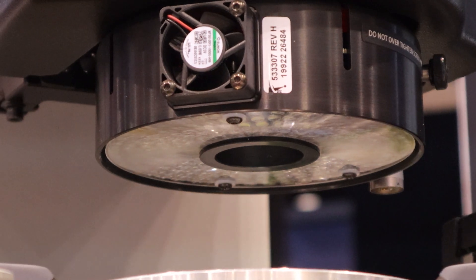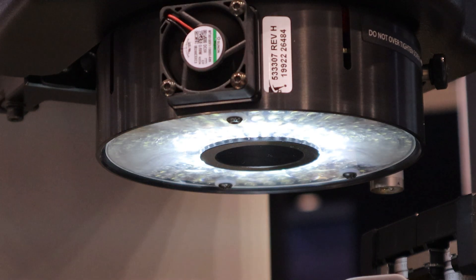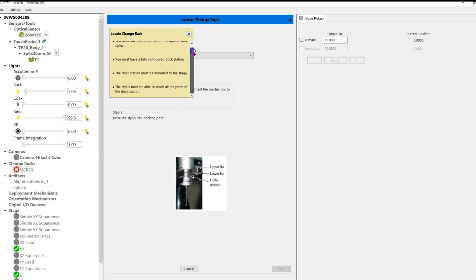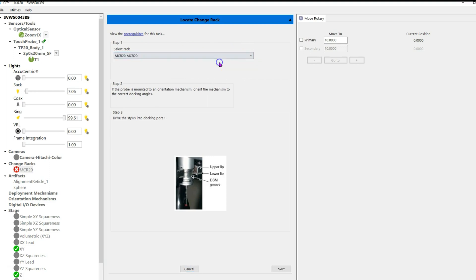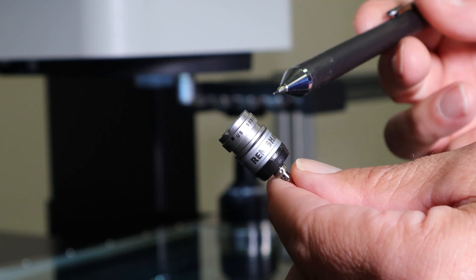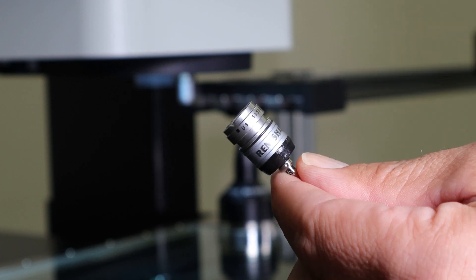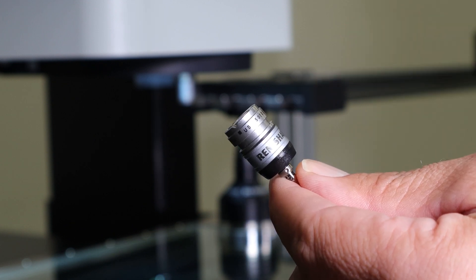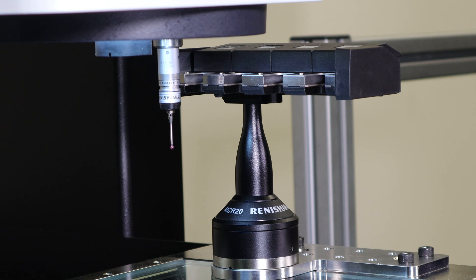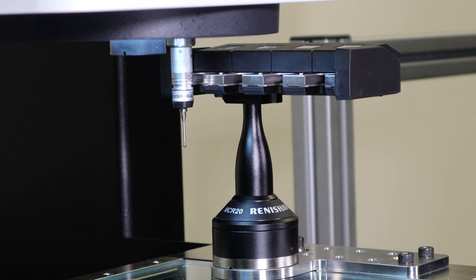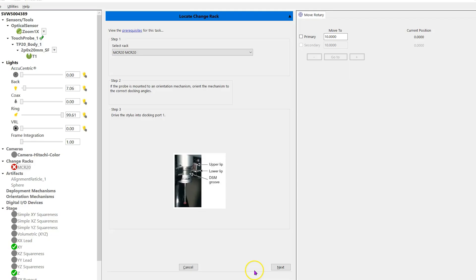Turn on the ring light so you can see what you're doing. In the top center of the screen above Step 1, you see Prerequisites underlined in blue—click on this to see the prerequisites for aligning a change rack. Select rack to align using the drop-down arrow. In this example we will select MCR20. Your stylus module has a groove—you're going to align this groove with the tool rack. Make sure the groove of the force module is between the upper and lower lip so it is centered. You'll see the picture on your screen.